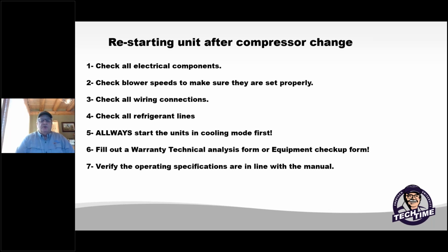And I guess it's really important to start your units in cooling first, even if you're in the heating season. We want the refrigerant to go through the filter dryer before it gets to the TXV. So always start everything in the cooling mode first anytime you change a compressor or on the startup of a new system. And also, we have the warranty technical analysis forms available through us or in the manuals.